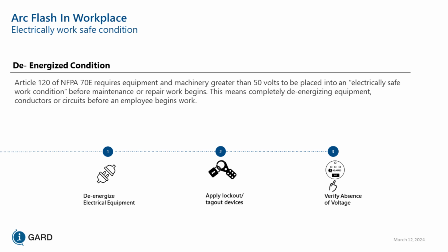One thing that's important is to look at secondary sources. So some panels have not only the mains of 480s coming in, but you also have maybe 120 volt AC or DC control power coming in. So you have to be aware of the particular equipment that you're working on. And this is why only qualified people are allowed to work on equipment. I've designed a lot of equipment in my life. I'm not qualified to work on any of it. So the employer determines who is qualified to work on their electrical equipment. Even though I may design something, if I go into someone else's facility, I'm not qualified to work on it.